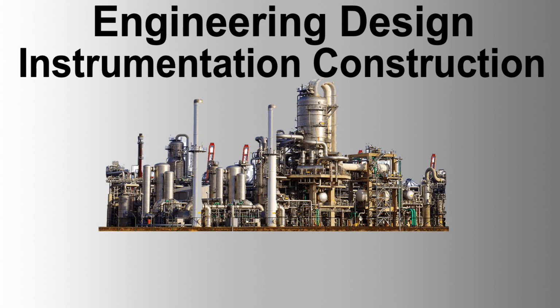Completion and handover. Upon successful completion of loop testing, a comprehensive report shall be prepared summarizing the results of all tests. The completed loop test documentation shall be reviewed and approved by the relevant authorities before the system is handed over for commissioning. Any outstanding issues identified during loop testing shall be resolved to the satisfaction of the company before final acceptance.